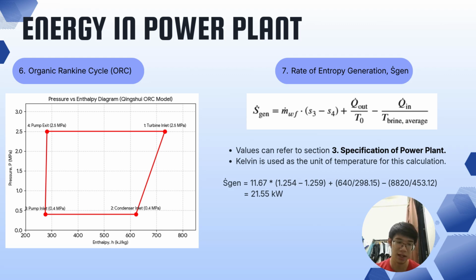At this point, the isobutane reaches the pump, and the pump increases the pressure of the isobutane back up until 2.5 megapascal again. Then the isobutane enters the heat exchanger, where it absorbs heat again, and the enthalpy rises from less than 300 up to more than 700. So this is how the cycle goes for the power plant.